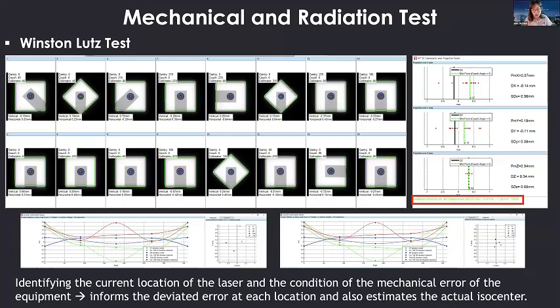We are really satisfied with the RIT analysis software because this program is very helpful in identifying the current location of the laser and the condition of the mechanical error of the equipment, because it informs the deviation error at each location and also the estimated and actual isocenter, things like that. Therefore, when the result exceeds the tolerance, like 0.5 millimeter, we can determine the cause a little faster.